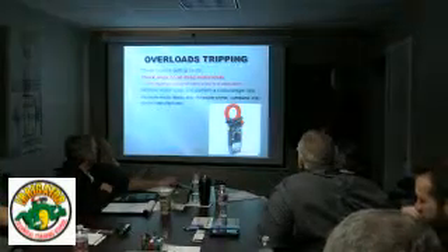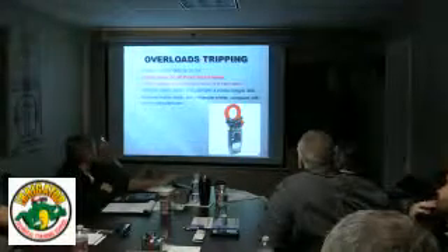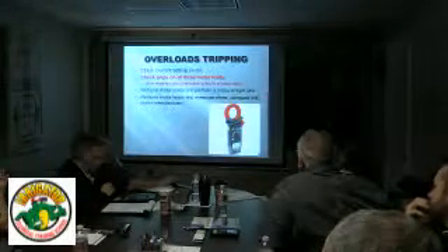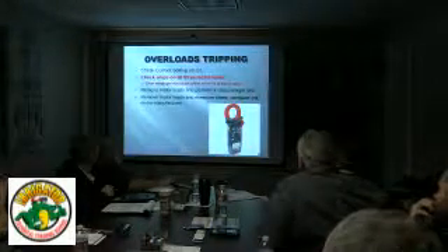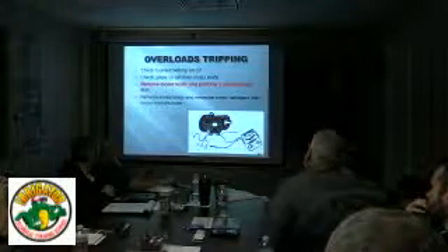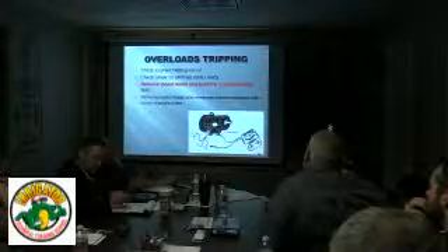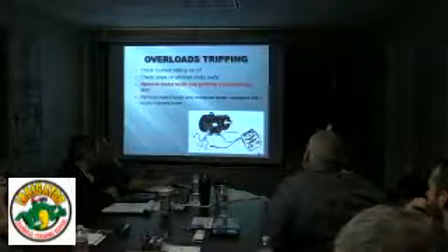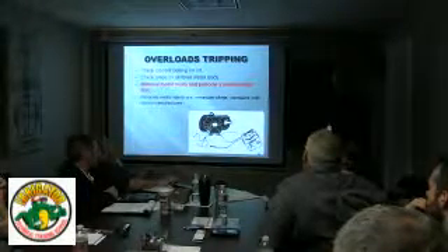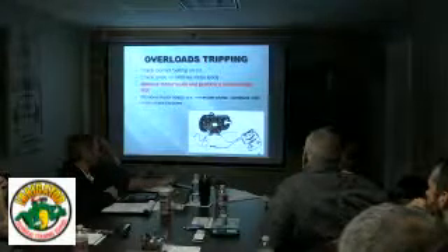Again, amp check the motor with a clamp on amp meter, on the motor leads or even on the input to the drive or whatever it's going to, you can check. Also, motor meg, you may have to meg the motor. Always remember to remove the leads from the drive before you do a motor megger test. Those will put out either, depending on the setting, 500 volts or 1,000 volts. And when you do a motor megger test on a motor, it could damage the input to a drive if you don't disconnect it from the drive. So always make sure that you disconnect the leads from the drive.